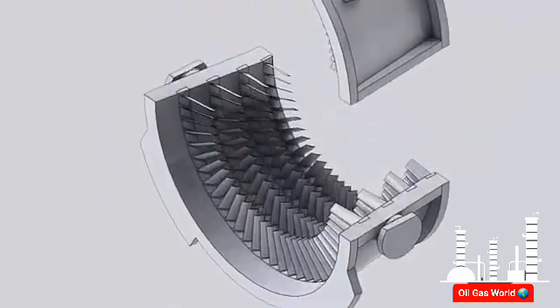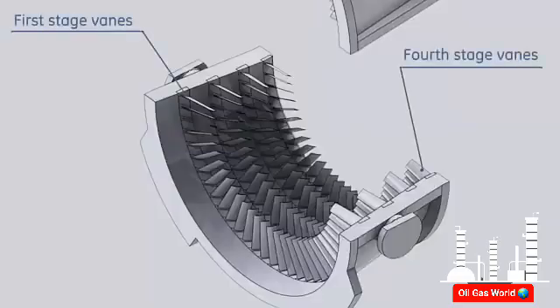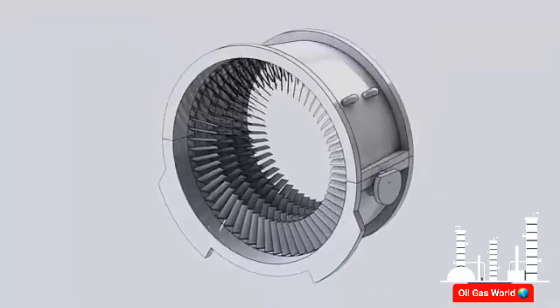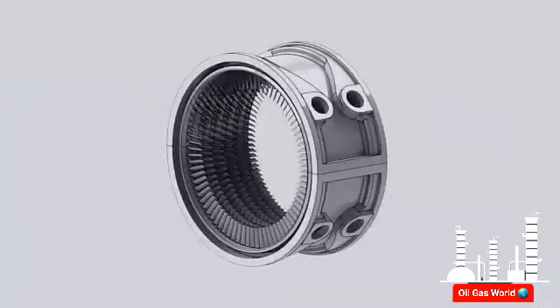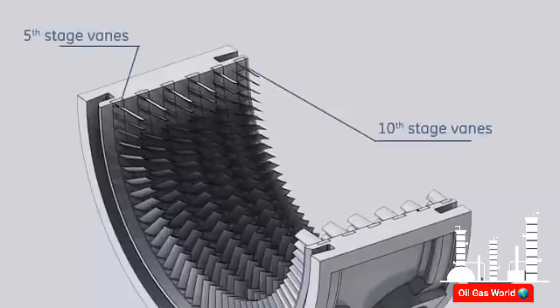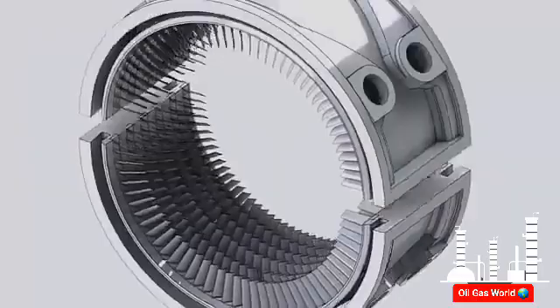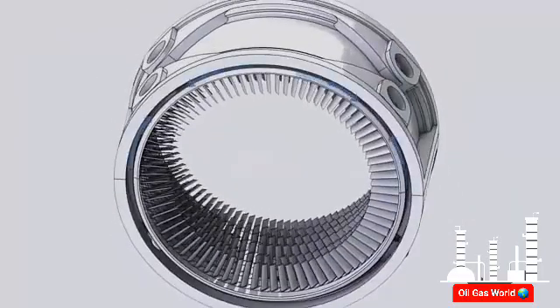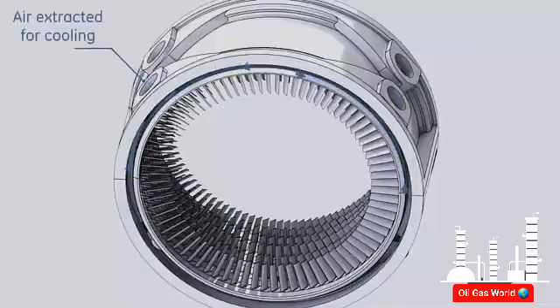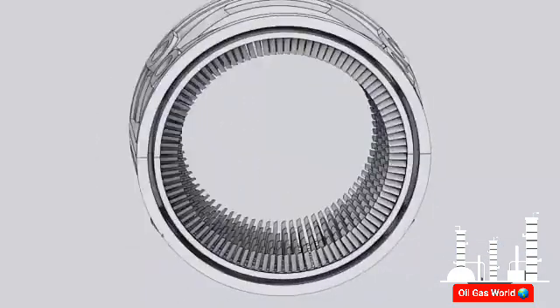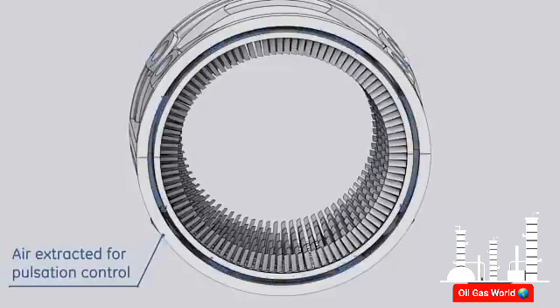The forward casing contains the first four compressor stator vanes. The lower half is equipped with two trunnions, used with other trunnions on the turbine shell to lift the gas turbine to or off the turbine base. It also features a mounting point for the forward turbine support plate. The aft casing contains the fifth to the tenth compressor stator vanes. A groove machined at the forward face around the fifth wheel blades allows air extraction for cooling and sealing through two ports in the upper half and two on the lower half. Another groove is machined around the eleventh wheel blades, where air is extracted for surge protection during transient operation.